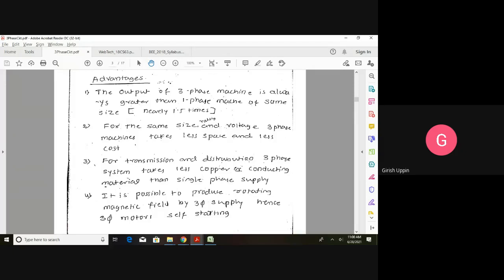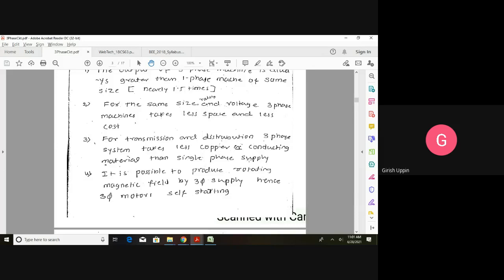In a single-phase system I would require two wires — one phase and one neutral — but in three-phase with delta connection I need only three wires, so one wire is saved. Using star connection we have four wires, but even so we save copper compared to having separate single-phase systems. It is also possible to produce a rotating magnetic field using three-phase supply, and hence three-phase motors are self-starting — we will see this in more detail when we deal with motors.